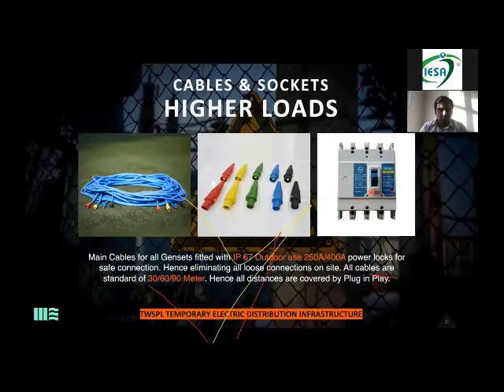So again, bigger load, bigger cables. So where we are using MCCBs, I'll give you an example. When somebody is asking for bulk load, it could be your sound, light, LED, or your AC guy who says, give me 200 kilowatts on the right hand side and give me 200 kilowatts on the left hand side of the hangar. So again, the genset maybe is a 380 kVA or a 500 kVA. What we do, we lay cables as per the size of the load that has been asked from us.